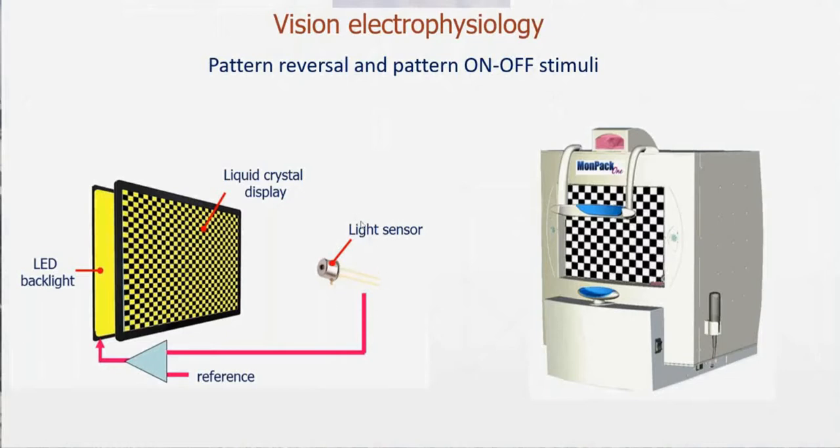So this guarantees that we have constant luminance and no transient flash for pattern reversal and also for pattern on-off stimulation.